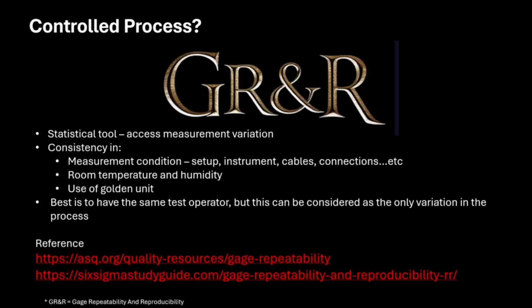So basically, you want a group of operators that will run the tester when you try to generate the pass, fail, and borderline golden units. So you predetermine, let's say, 15 units, 5 in each category, and then you get a group of operators over a span of a few days. Every day will be morning, afternoon, and late in the shift, and you make sure that all of them have a good combination of variations. Then you get the average of the readings, and you see whether the pass will still maintain pass, and the fail will still fail. The borderline will give you a borderline reading.